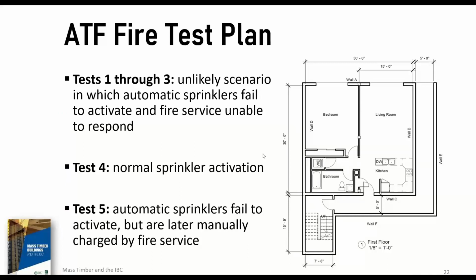So there's the plan view schematic of the actual compartment that was tested. You can see the corridor there, the stairwell. There's a 20-minute door at the compartment into the unit, and there's a 90-minute door at the end of the hallway going toward the stairwell. So tests 1 through 3 in both the upstairs and downstairs compartments were to simulate the unlikely scenario that the fire suppression system fail and the fire service is unable to respond or unable to charge the standpipe.